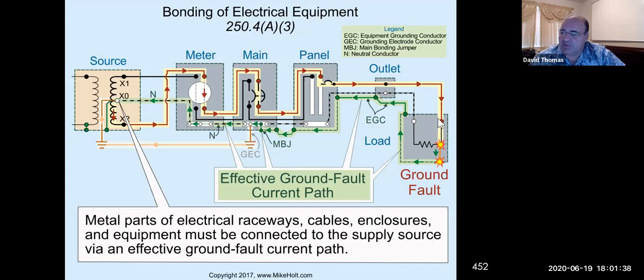Okay, so you can see here a wire has tripped against the frame. So the electrons are flowing on the red wire in this case from the transformer back this way. You can see the yellow pathway back, all the way back to the point that we ground, we've touched the panel or the enclosure. And now if everything's properly grounded, we would create a loop back to the system, back to the X0, which is in the transformer, allowing and facilitating this loop to now have a lot of current. So we bump up the current. We want it to be high enough to trip the breaker. So we have one breaker at the panel. We also have a main panel breaker. So we have two points that we might be able to trip in the system, and hopefully enough that it will protect the wires and won't damage the wires.